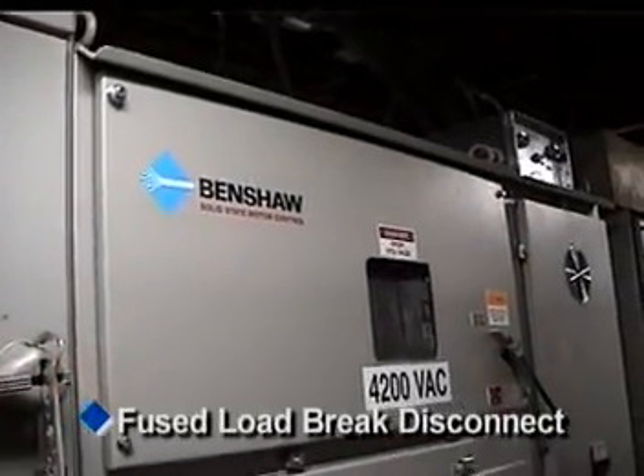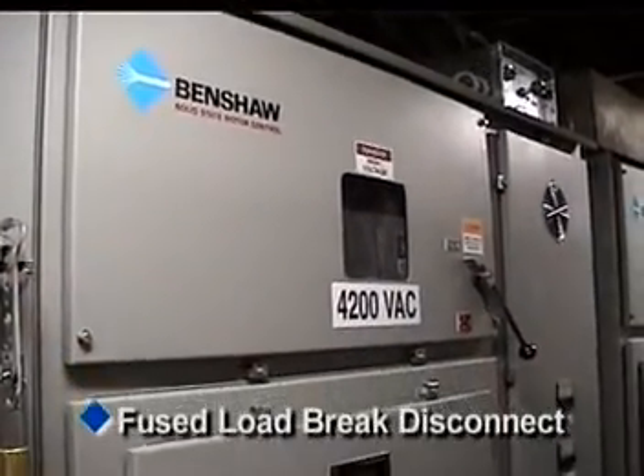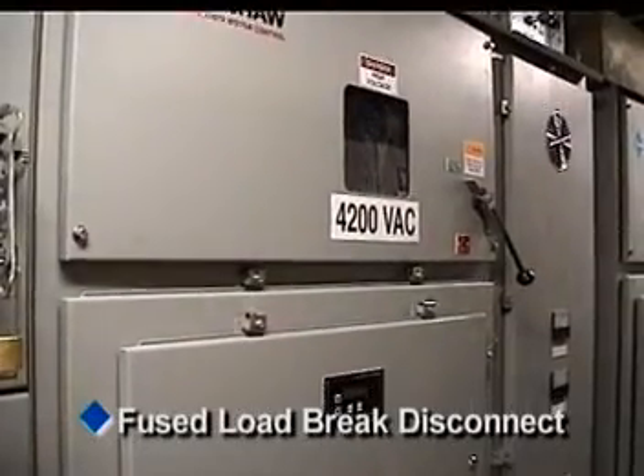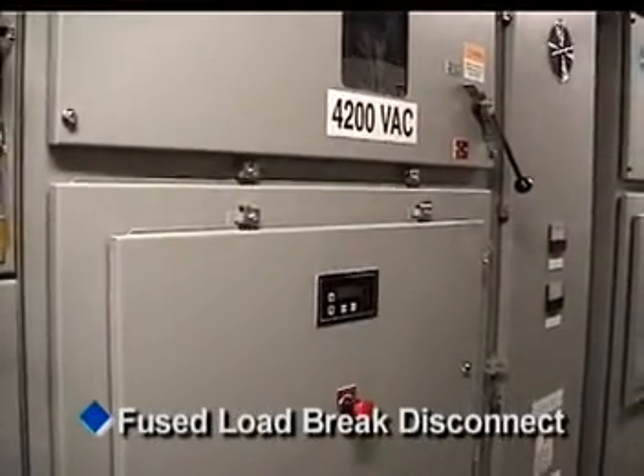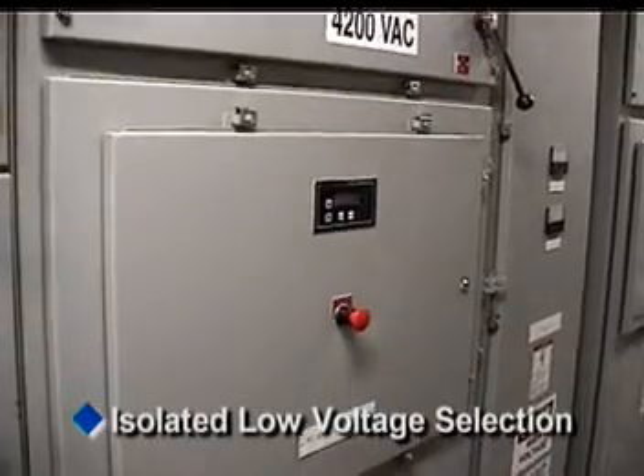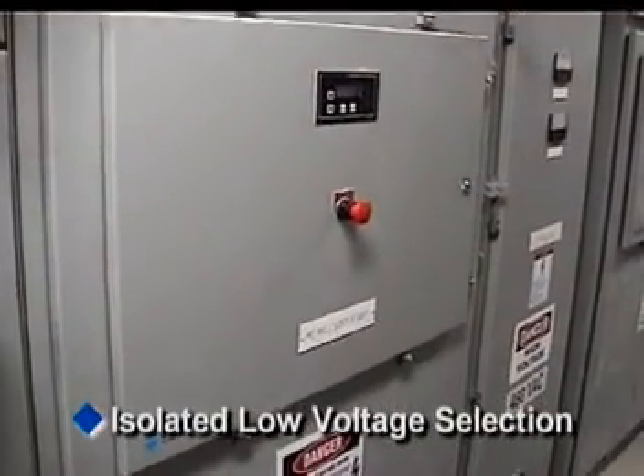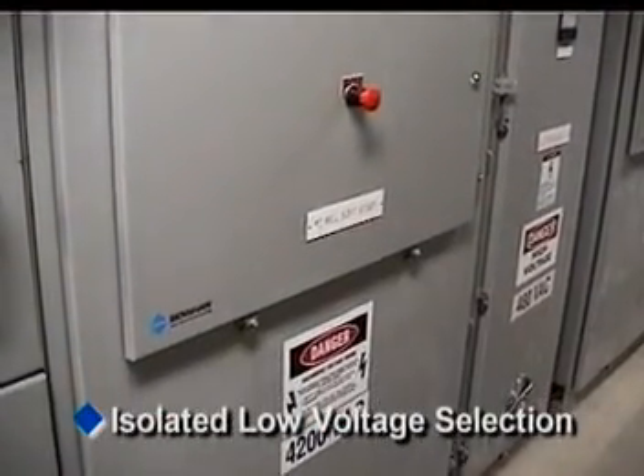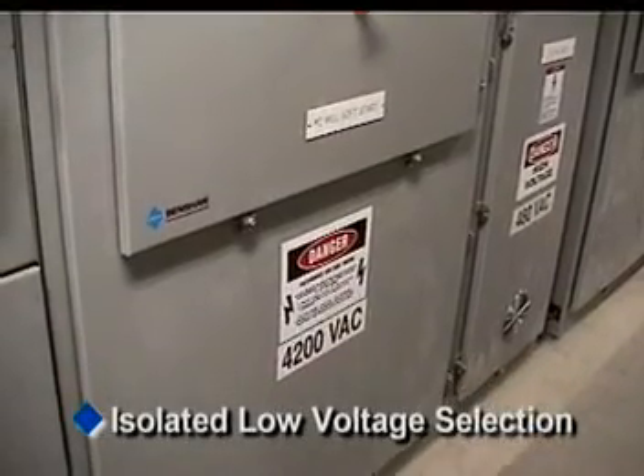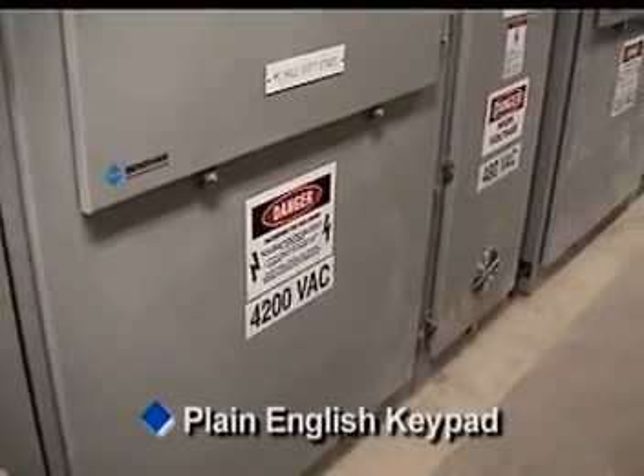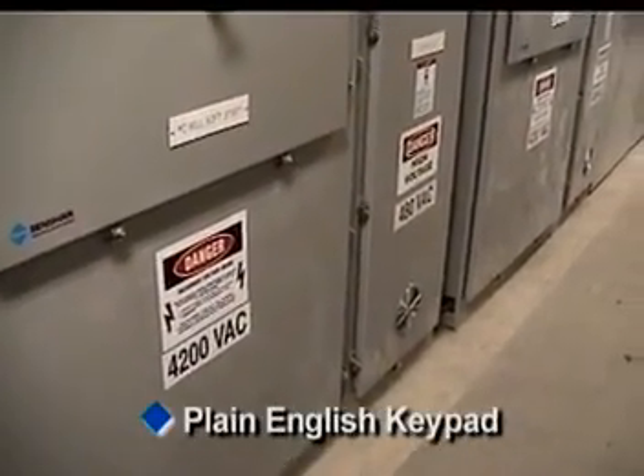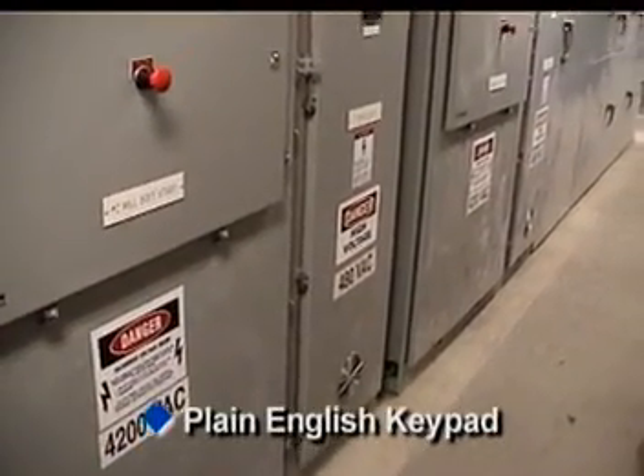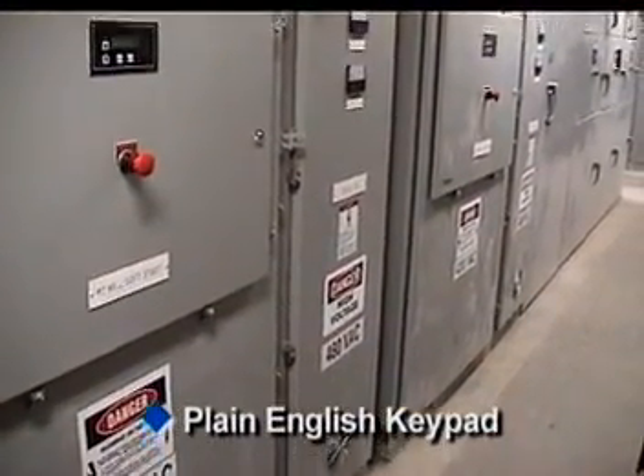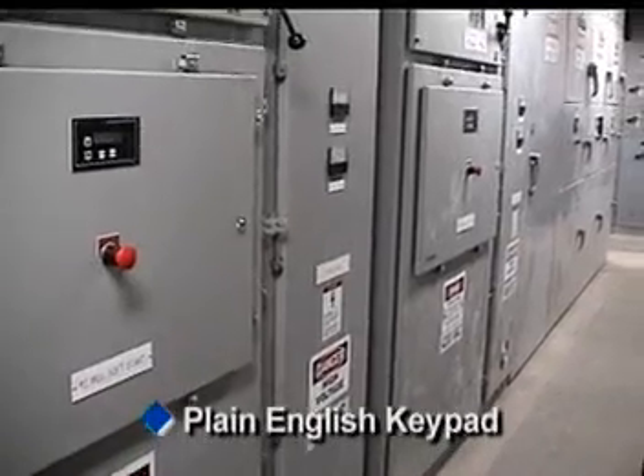Standard equipment includes a heavy-duty, fixed-mount, 5 kV load brake switch with visible blade window and padlockable handle mechanism. A low-voltage door-in-door section includes customer terminals, local e-stop, and LCD keypad for local setup, monitoring, and programming. For remote monitoring, Benshaw can provide a Windows-based software called ReadyView.